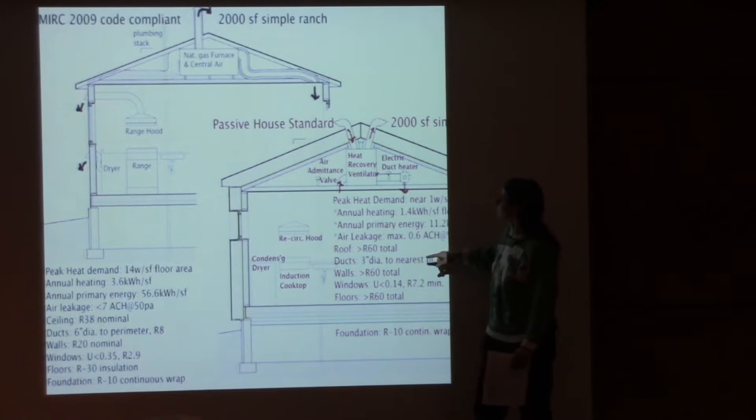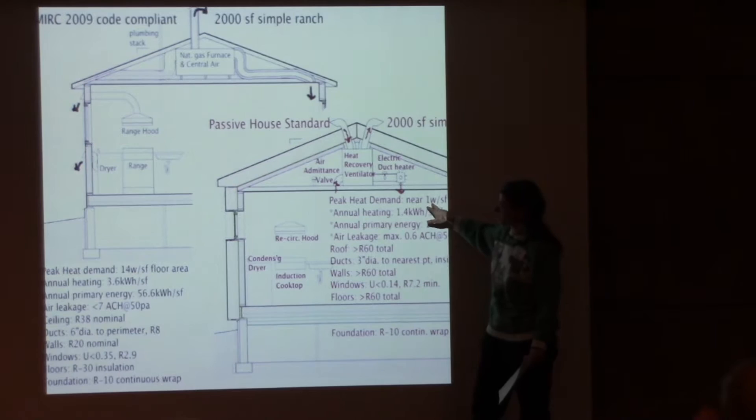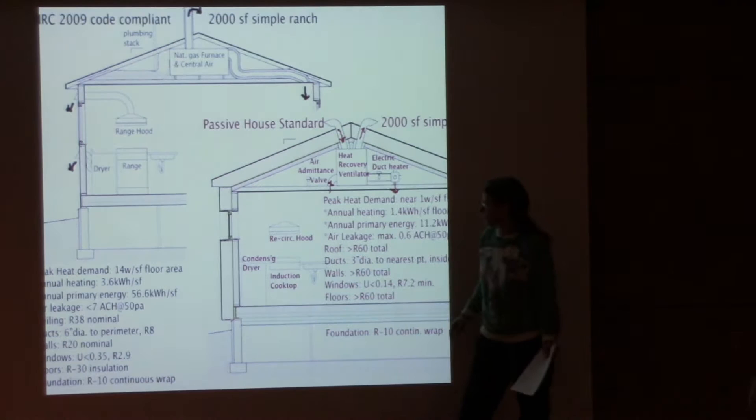Comparing a code-compliant building in Michigan to Passive House Standard: peak demand in a Passive House building is about 1 watt per square foot versus 14 watts per square foot. Annual heating is 1.4 kilowatt hours versus 3.6 kilowatt hours. Annual primary energy is 11.2 compared to 56.6.